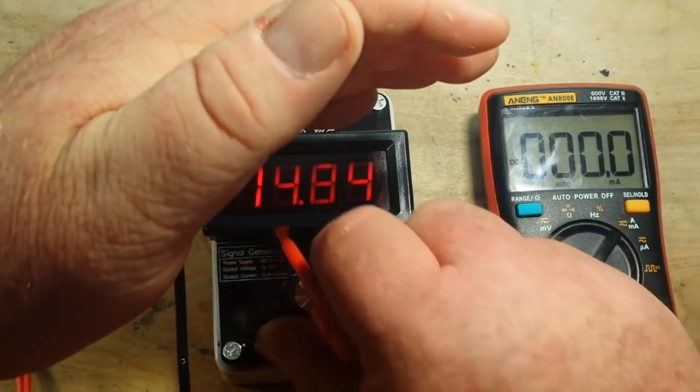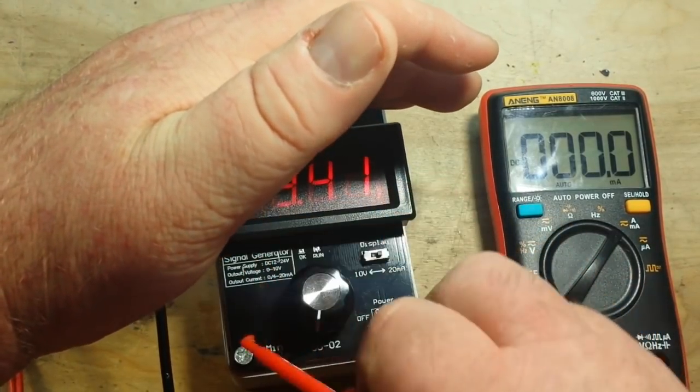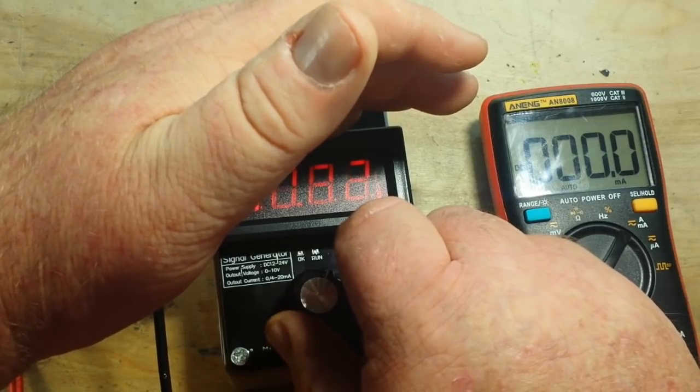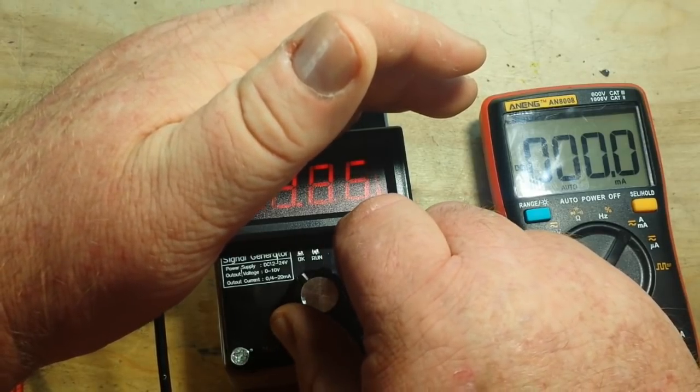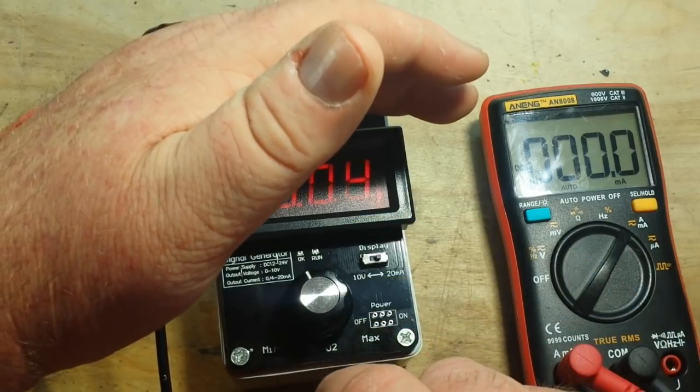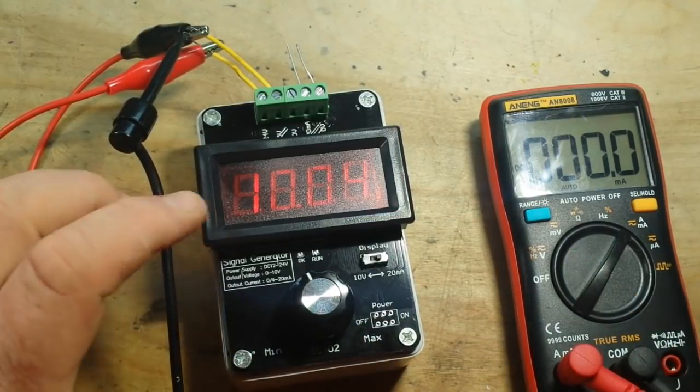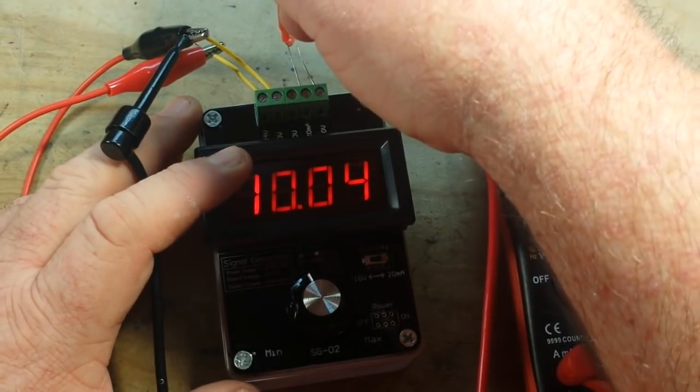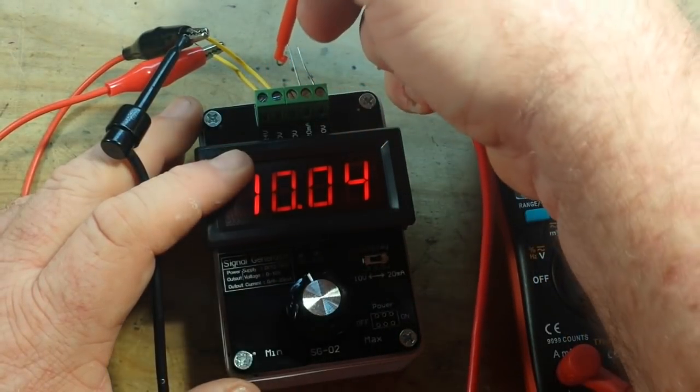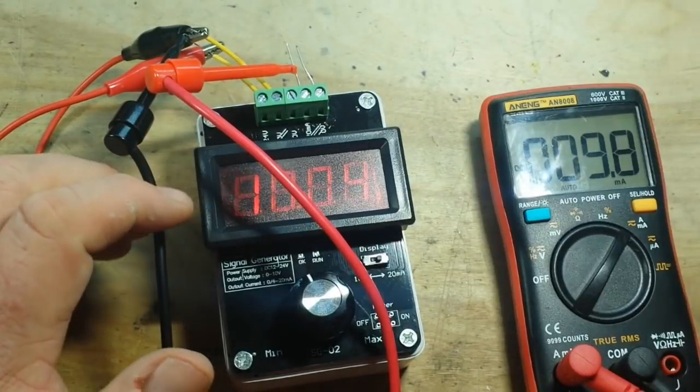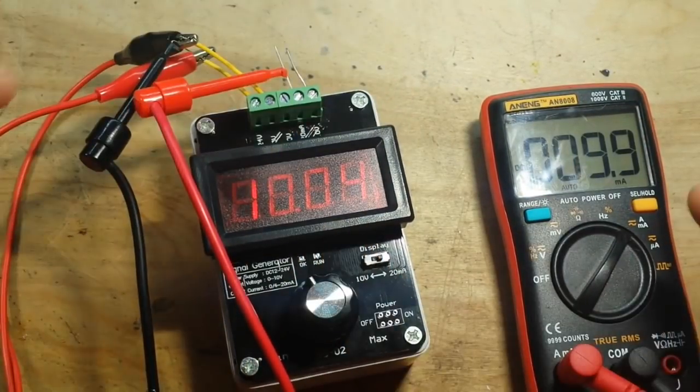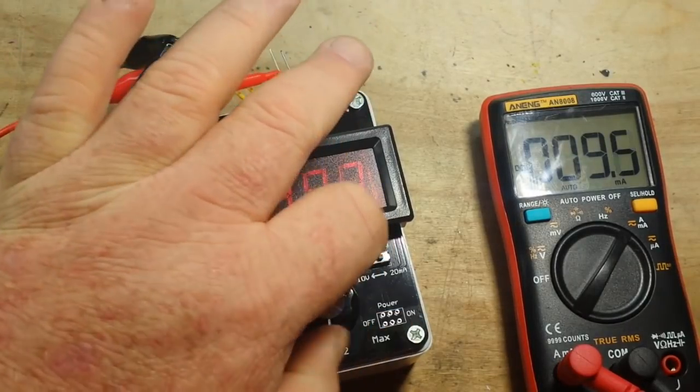So we'll turn this down. Let's get about 10 milliamps on here. Now we can hook up here to our milliamp reading. There you go. We're showing 10.04 here, 9.9 here. We can take it down or we can take it up.